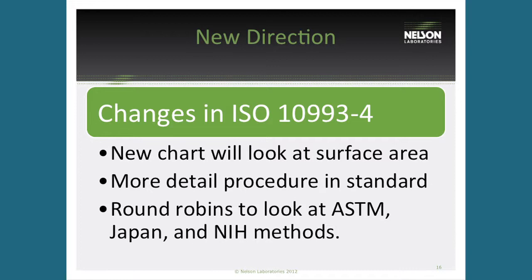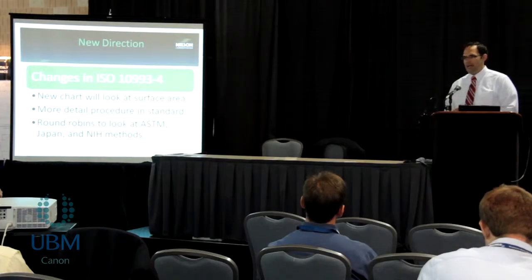If you run an ASTM and a Japanese method, do you get the same endpoints for the same device? To answer that, we're starting round robin testing throughout six or seven labs throughout the world to compare results from NIH, ASTM, and Japan, and also human blood versus animal blood. We want to look at the difference between the methods and the blood sources to see if we can put one single method in the standard that everyone should follow. The standard looks to have a more defined test method and more defined criteria around that method, as well as the updated chart.